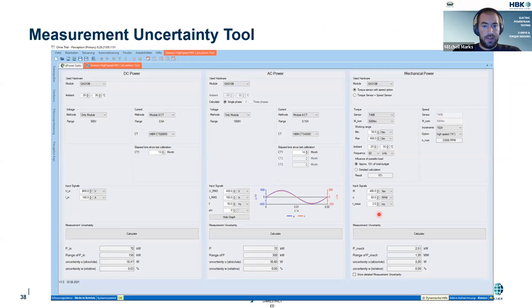And while we understand it is a complicated calculation for measurement uncertainty, for torque or for electric power, we offer a tool within our software suite for understanding the measurement uncertainty of a given operation point. So you plug in what your voltage, current, frequency, and power factor is, and we give you out what your uncertainty percentage and absolute uncertainty is. We try to make this easy. We try to make it less scary. So this is a really cool tool. Again, happy to discuss offline.